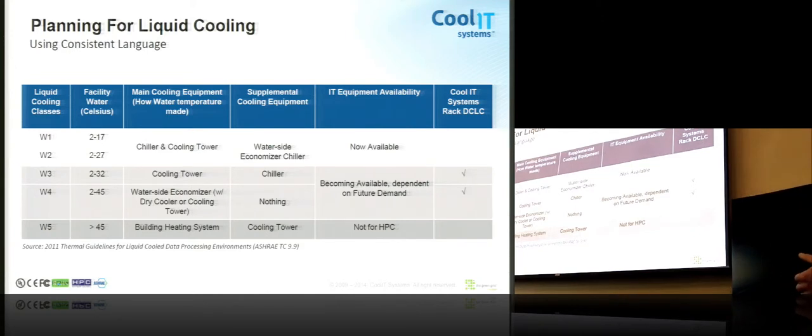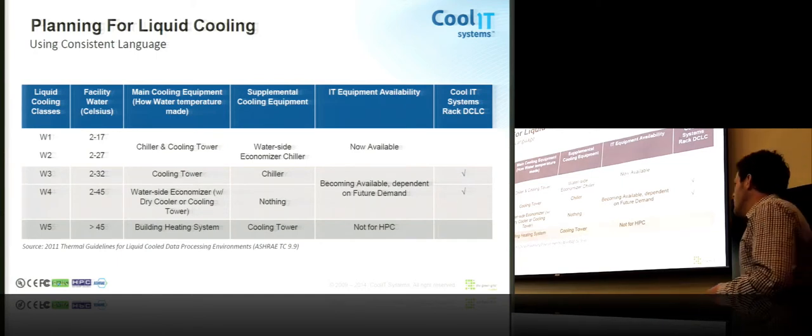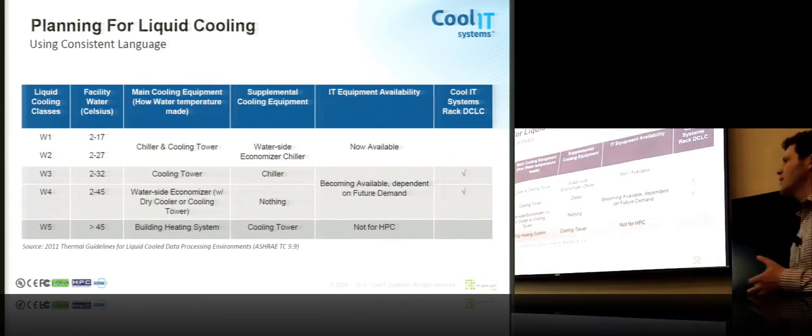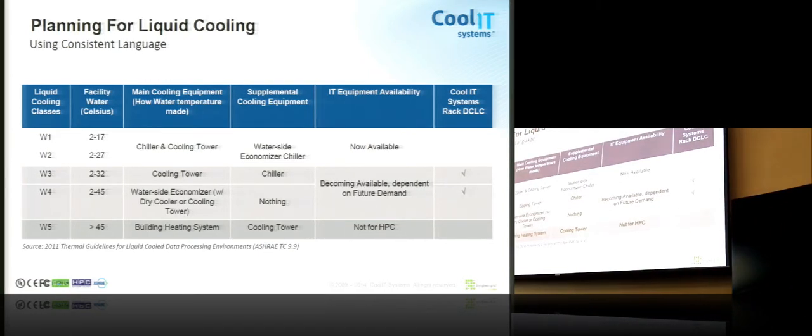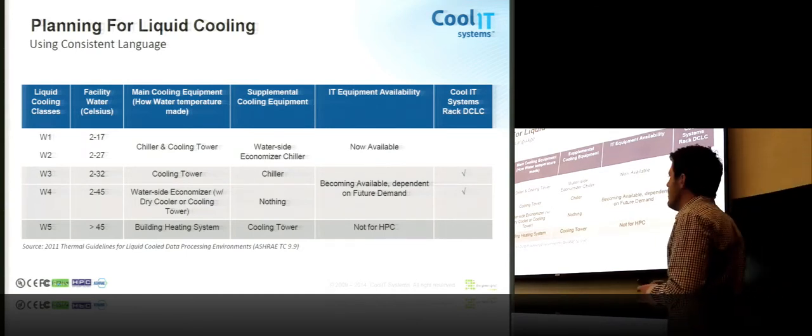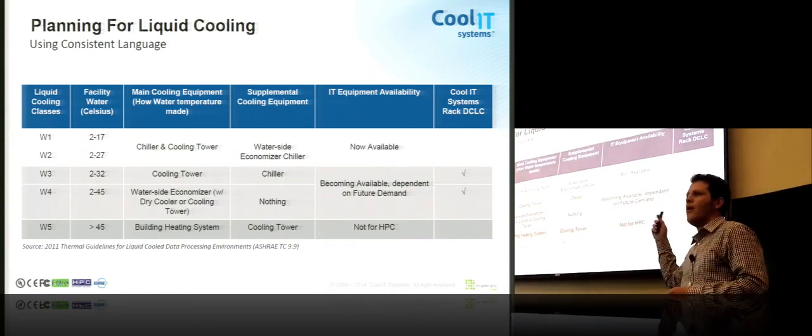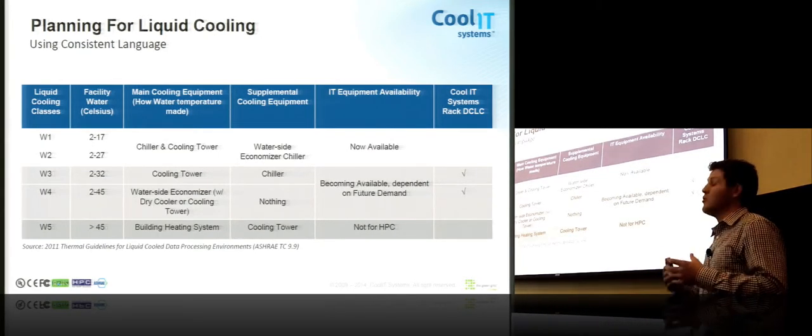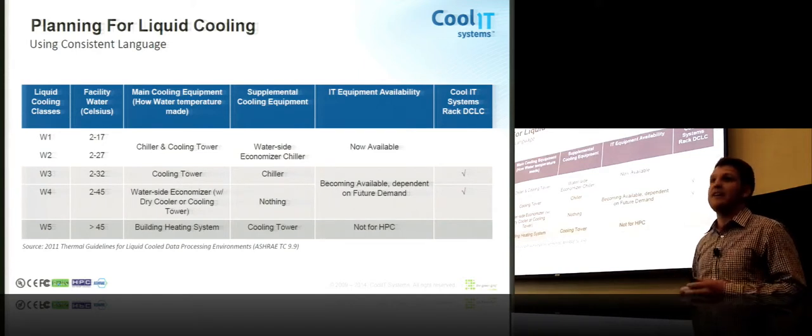For a long time I think we've used W1 water fairly well in the data center. That's chiller based water. W2 water takes it to the next step. It's 27 degrees Celsius water in some environments. NREL for example with their HP Apollo 8000 system can produce W2 water all year round with the dry bulb they have in that climate. Just using a cooling tower which is amazing.